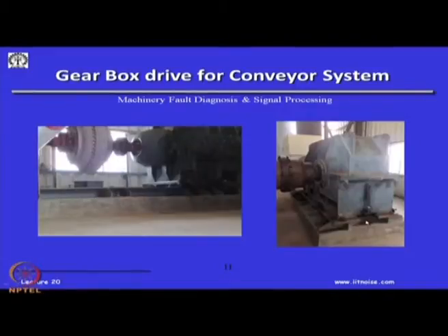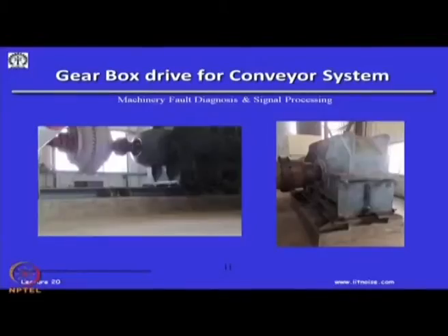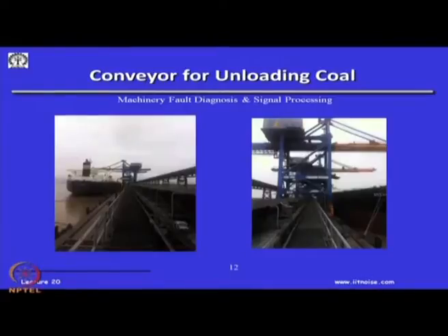On top of it, if you do not do a perfect alignment, a lot of sources of high vibrations can arise. No matter that you may have a very good new gearbox, new motor, new bearings, your misalignment in the foundation is going to give you high levels of vibrations.